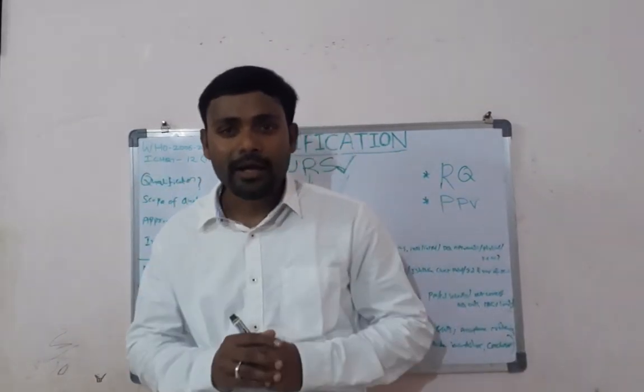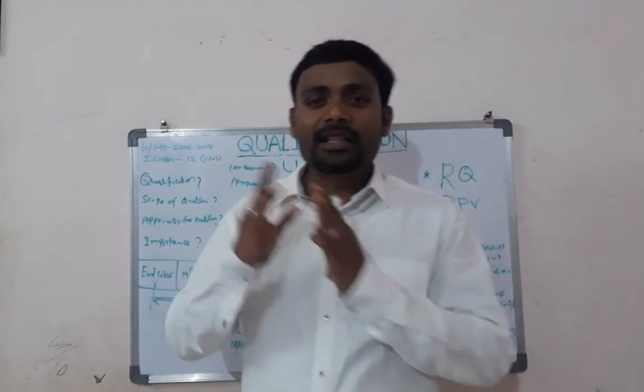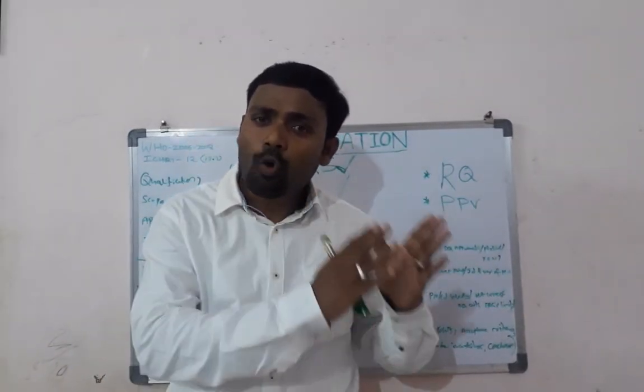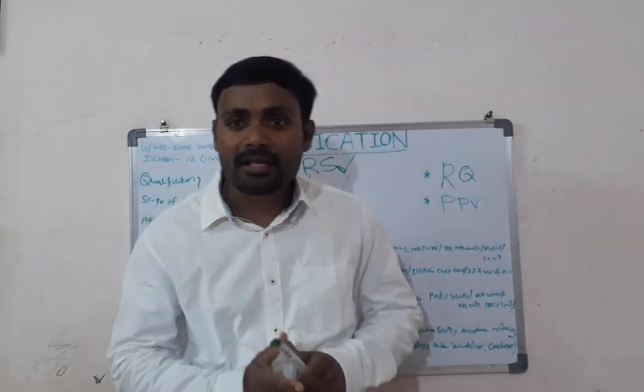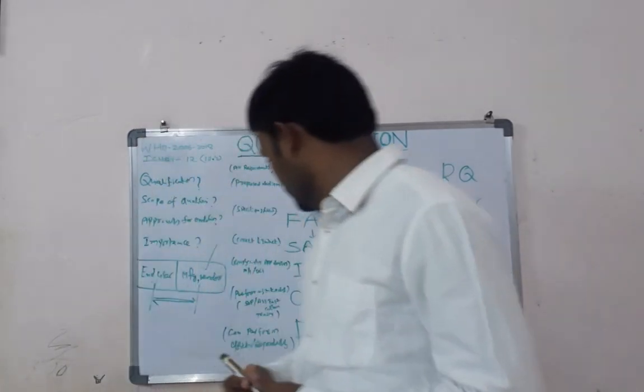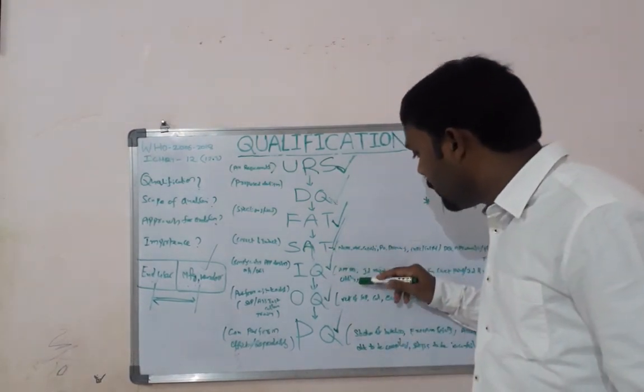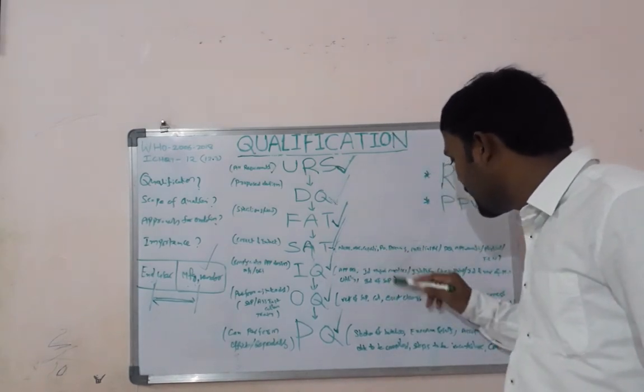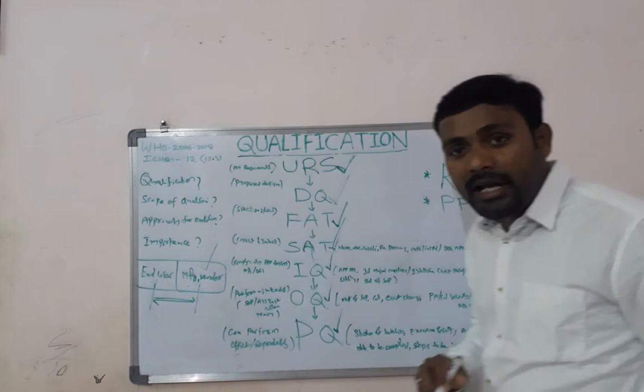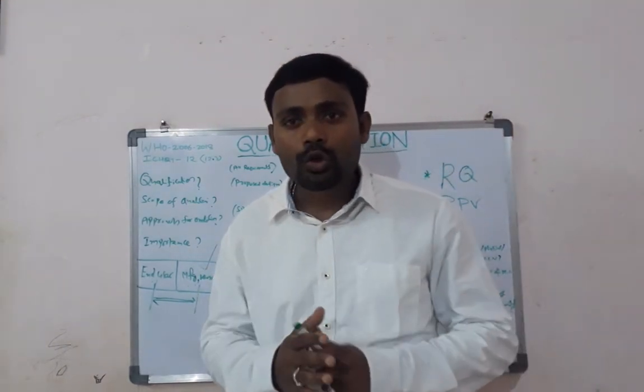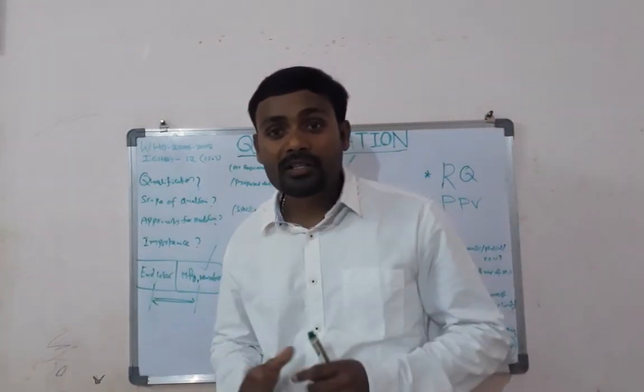Once SAT is complete, the equipment is ready to be installed at its designated location, and Installation Qualification (IQ) begins. IQ is a documented verification that an equipment or system as installed or modified complies with the approved design, vendor recommendations, and user requirement specifications. The IQ report covers DQ approval, identification of major components and accessories, installation checkpoints, MOC and utilities verification, and SOP identification.